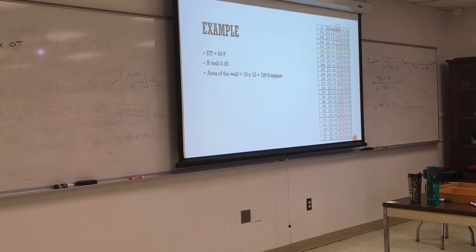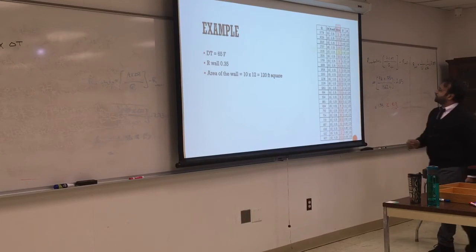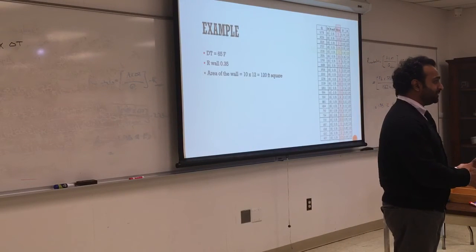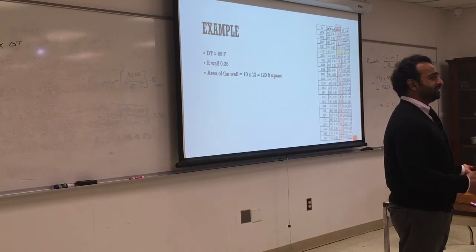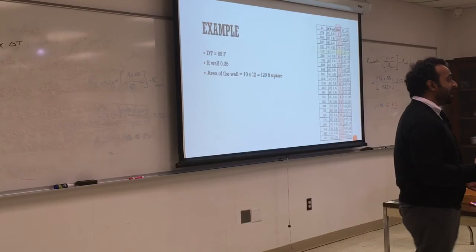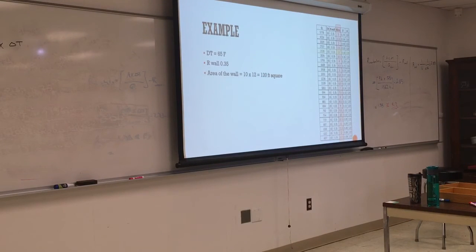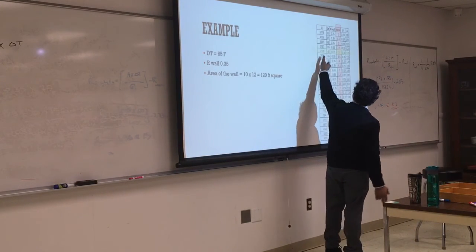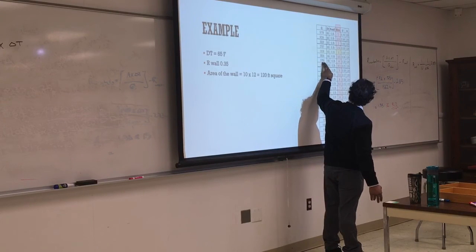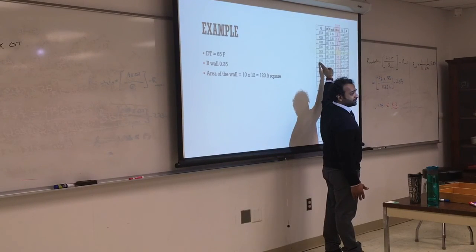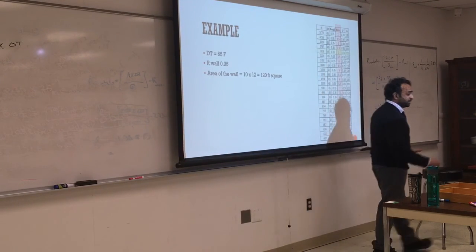And again, this is the calculation for it. Of course, you don't have to go to this extreme. You can go and see what is available. We have 2, 4, and 6. Do the math for those three, see which one gives you the biggest change, and just keep it at that. It's impossible to have zero heat transfer. You will always have heat transfer unless you have your house designed as a thermos. It's going to be there, but we want it to be as small as possible. I mean, going from 6,000 to around 2,000, or 4, is even better. That's enough to have a significant reduction in heat transmission, which is not that bad.